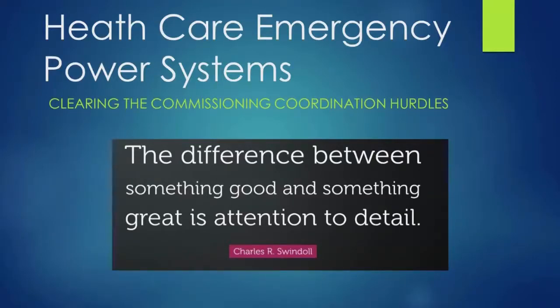We're there when the NFPA 110 startup and load bank testing is completed. As part of documenting that NFPA 110 adherence, I'm not the one providing the documentation, but the vendor is there and I'm watching them do it. So I ask, hey, I want a copy of the NFPA 110 documentation you're completing today—I want to see it fully documented. And by the way, I have my own; I'm documenting what you're doing. For the projects I'm on, that's something I see on a regular basis.